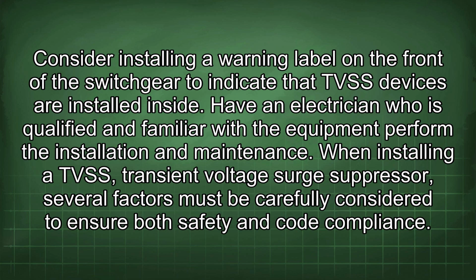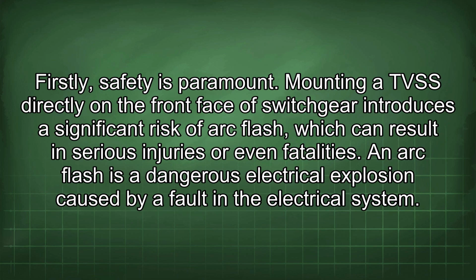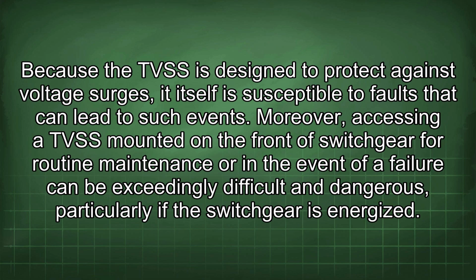When installing a TVSS transient voltage surge suppressor, several factors must be carefully considered to ensure both safety and code compliance. Firstly, safety is paramount. Mounting a TVSS directly on the front face of switchgear introduces a significant risk of arc flash, which can result in serious injuries or even fatalities. An arc flash is a dangerous electrical explosion caused by a fault in the electrical system. Because the TVSS is designed to protect against voltage surges, it itself is susceptible to faults that can lead to such events. Moreover, accessing a TVSS mounted on the front of switchgear for routine maintenance or in the event of a failure can be exceedingly difficult and dangerous, particularly if the switchgear is energized.